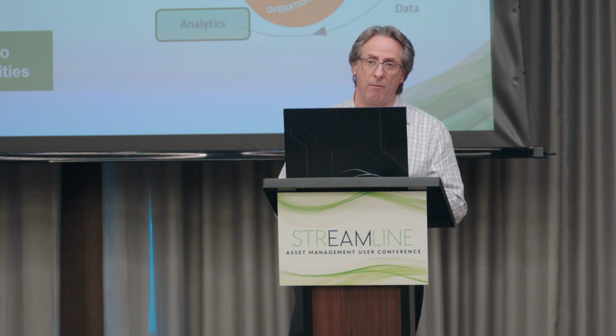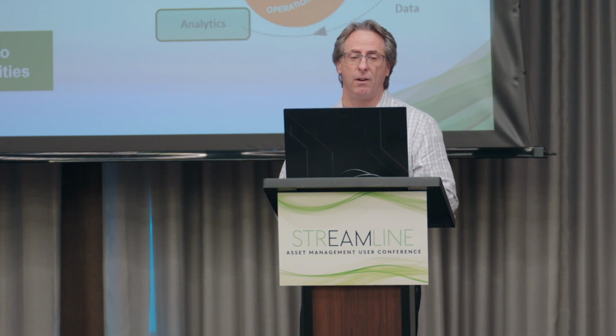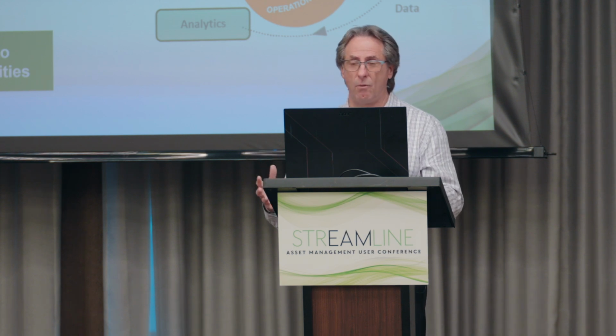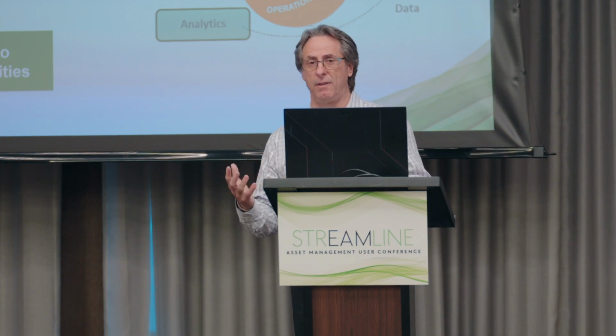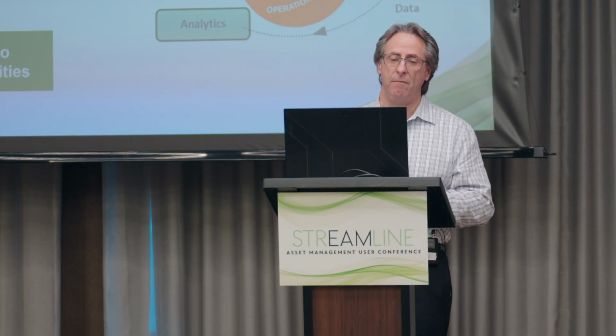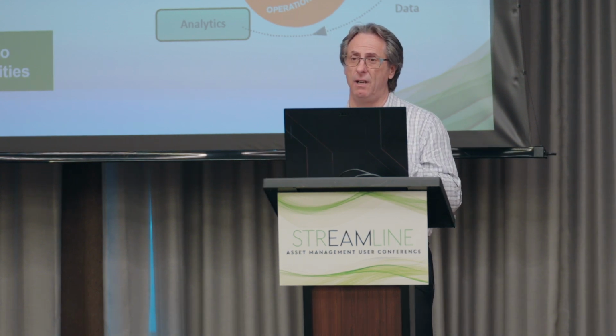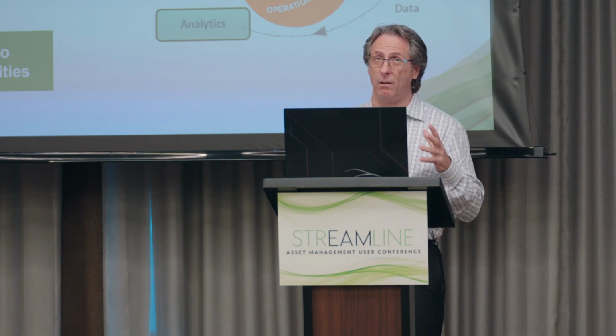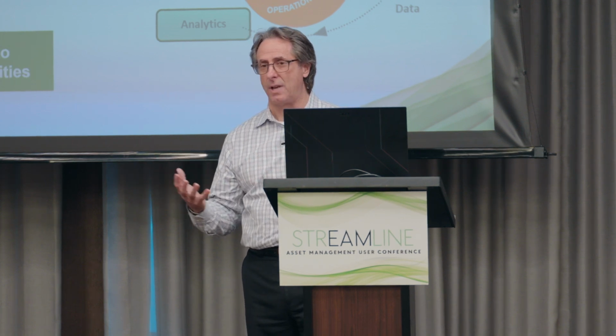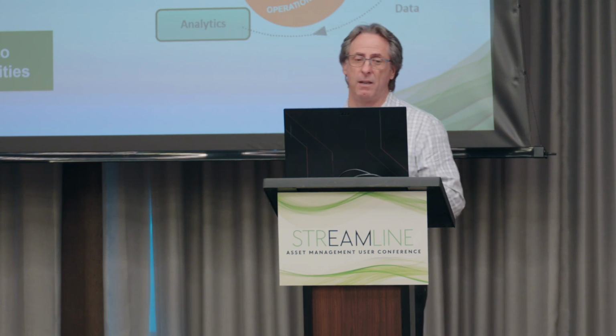Then we also want to look at the effectiveness of our maintenance. Are we finding failures? Are we having to do rework? Very often, after our maintenance crew goes out and does the work, we start the equipment back up, and within a day we have to shut it back down and go out and do rework. So we absolutely want to capture that. And then another piece is the efficiency of the maintenance side. We want to look at our planned estimates of time and material versus the actual of what's being used, because that tells us how efficient we are in the execution of the maintenance.